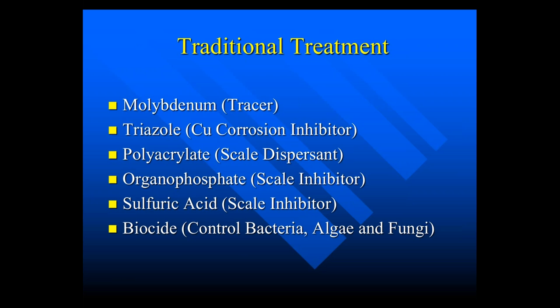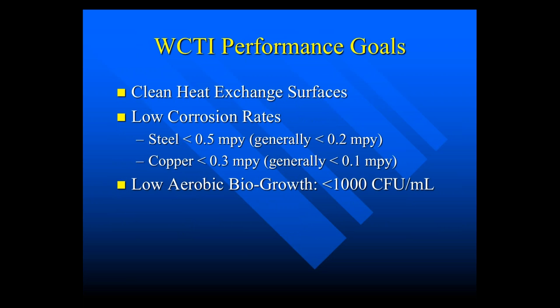With the zero blowdown approach, we still need the tolytriazole and a biocide, but nothing else — well, and silica. Performance goals include clean heat exchange surfaces, achieved with low hardness, low corrosion rates, and low bacteria growth. This is the one area that we did not achieve in this project.